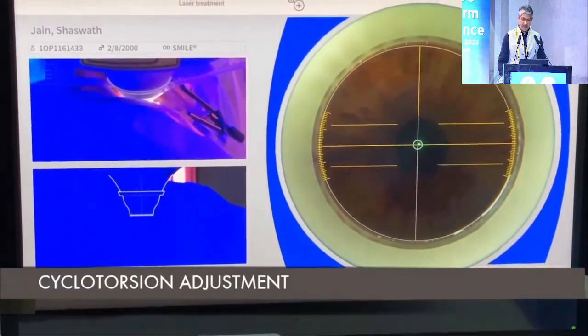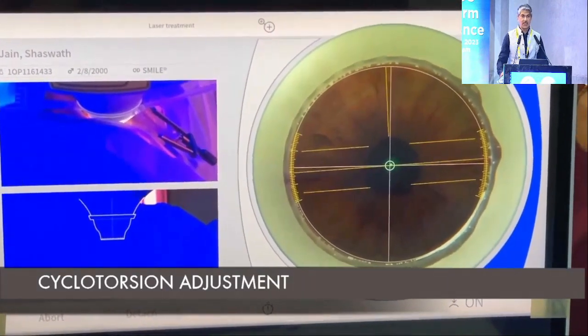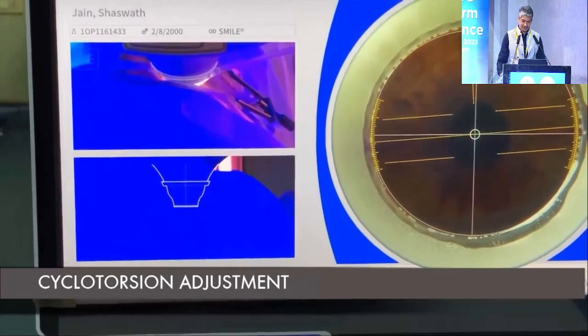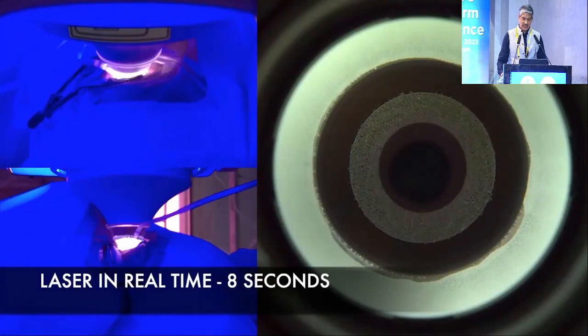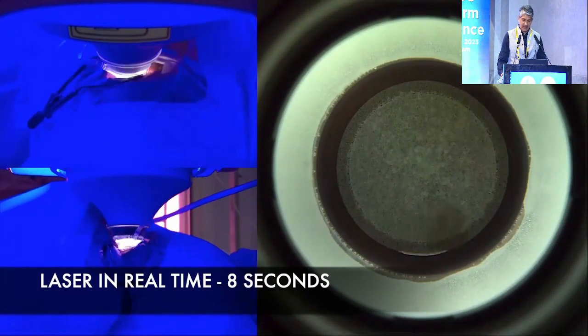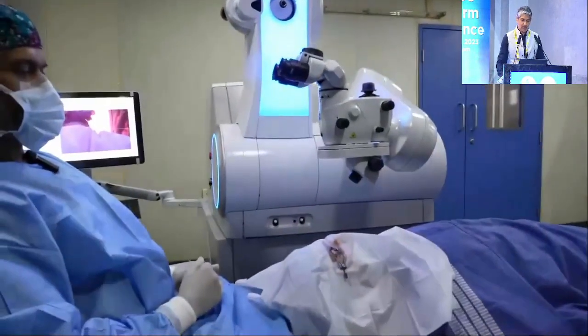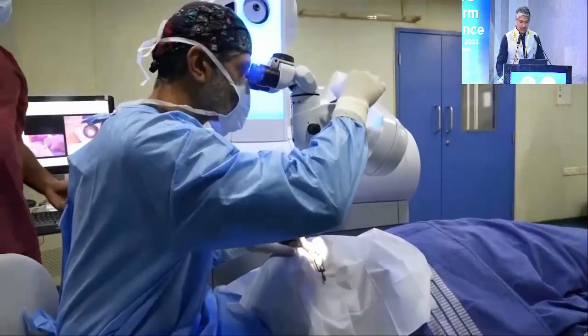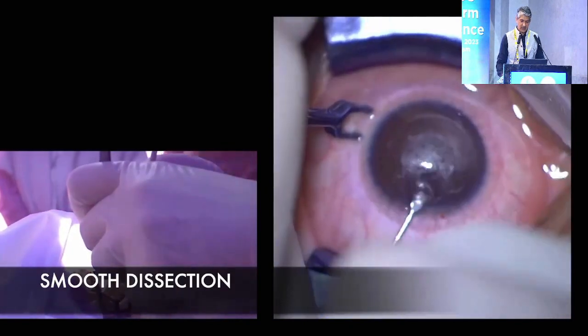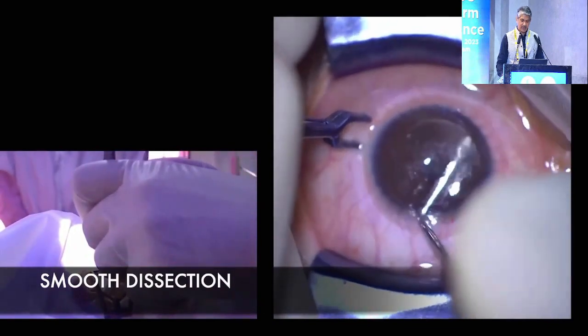The VisuMax 800 has a centration guide where you can center on the visual axis, which is different from the 500. It also has cyclotorsion adjustment — you mark the 0-180 degrees and then by rotating the joystick you can rotate the axis of placement of the treatment to compensate for static cyclotorsion. The laser itself is much faster at 2 MHz, taking about 8 seconds for a 6 mm zone and 10 seconds for a 6.5 mm zone, with a smooth dissection and no OBL.